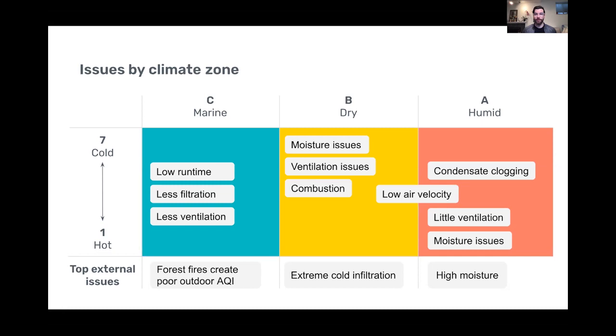And you also have little ventilation because you're bringing in very hot and humid air. And so a lot of people will go with the minimum ventilation, and some people go with no ventilation at all, because it can cause a lot of microbial growth and mold and other issues. So a lot of this humid environment, you're dealing with water, you're dealing with moisture. That's some of the most complicated and damaging issues. So that's definitely the biggest issue in this climate zone.